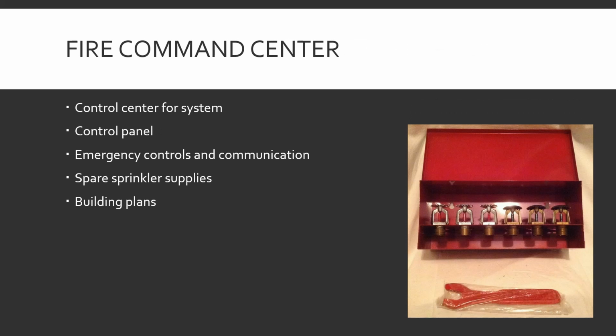Fire Command Center. Bigger buildings, big facilities, paper mills, that kind of thing, might have an actual dedicated Fire Command Center. In other places, there really isn't. Like places I've worked, all this stuff is kind of spread around. Where I've worked, the control panel for the fire alarm system is in the maintenance room, where the sprinkler system is built in, with the sprinkler supplies because that's convenient. The building plans are in the maintenance room, or the little workshop area.